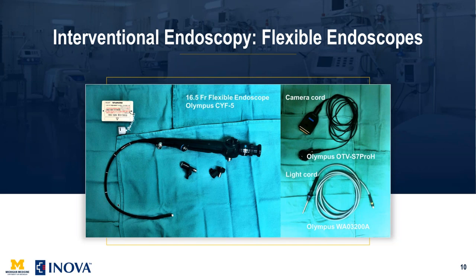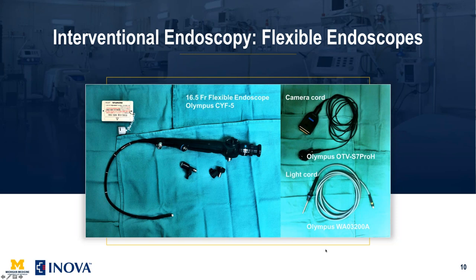The 16.5 French flexible reusable endoscope is one of the workhorse scopes. It can be used once, autoclaved, and used on the next patient. It has an area where the camera attaches, an area where the light source attaches, and a working channel where fluid can be administered and a variety of devices can be placed. One end of the camera cord attaches to the endoscope itself, and the other end attaches to your tower. The light source is emitted from the tower.